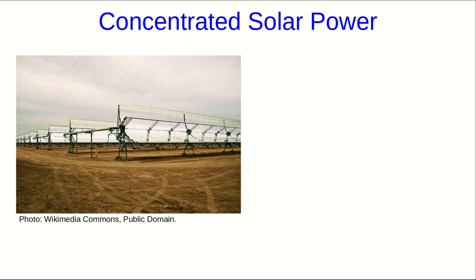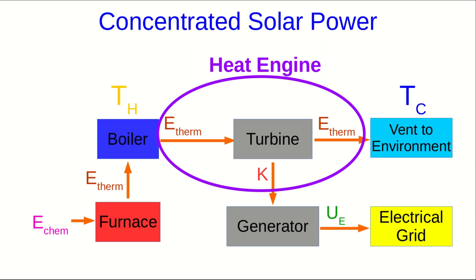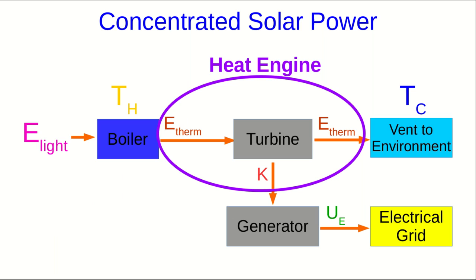One particular setup for concentrated solar power has pipes with fluid flowing through them and parabolic mirrors reflecting sunlight onto them to heat up that fluid, which is then used as the hot reservoir for a heat engine. Another type is a tower, where arrays of mirrors reflect sunlight up to a central tower that also has fluid flowing through it to run a heat engine. More or less, all setups share the feature that mirrors concentrate light onto a fluid to heat it — and from that point on, it's a thermal power plant, just like a fossil fuel plant, except we're converting light energy into thermal energy instead of chemical energy.